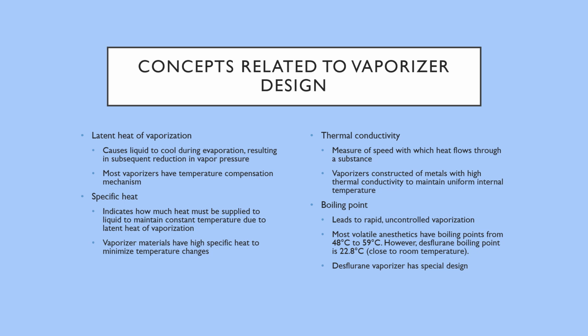The difference is with Desflurane, which has a boiling point of 22.8 degrees, which is very close to room temperature. So if the operating room is at or above room temperature, it could cause boiling with Desflurane. So Desflurane vaporizer has a special design.